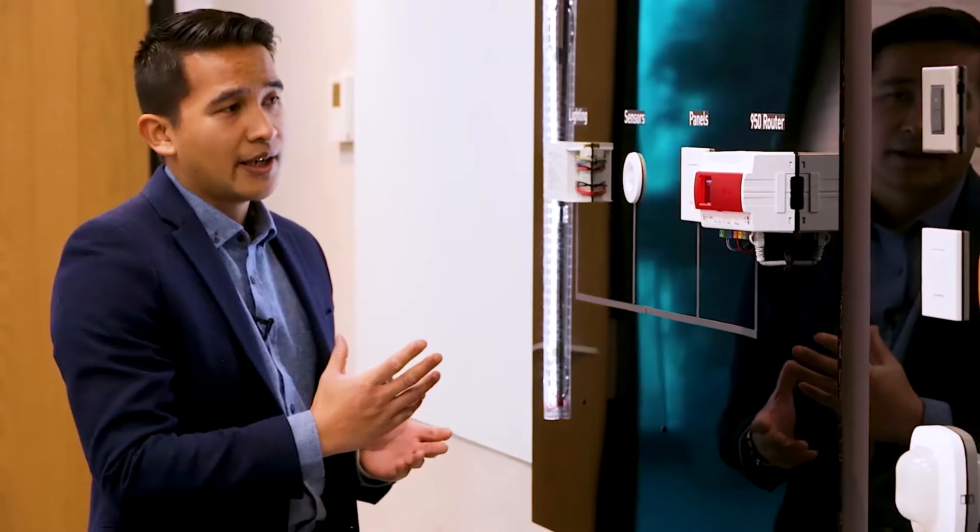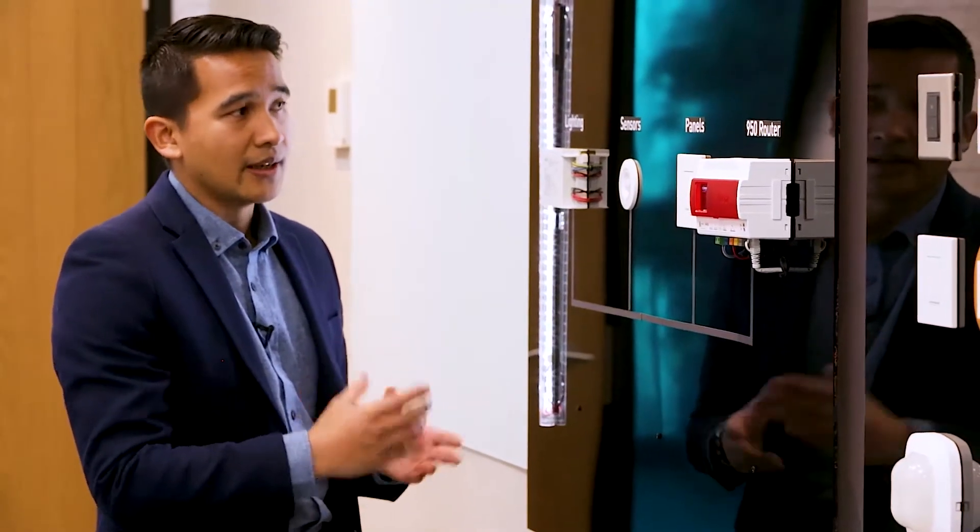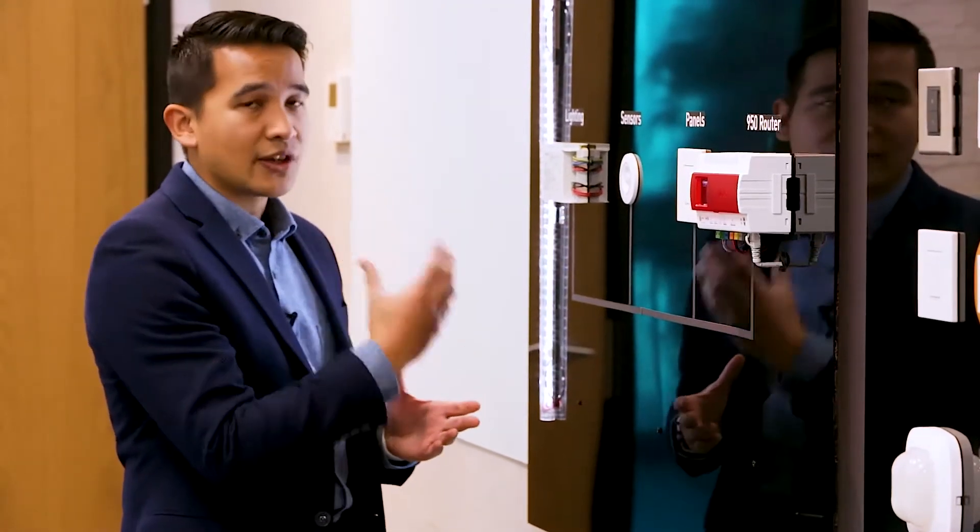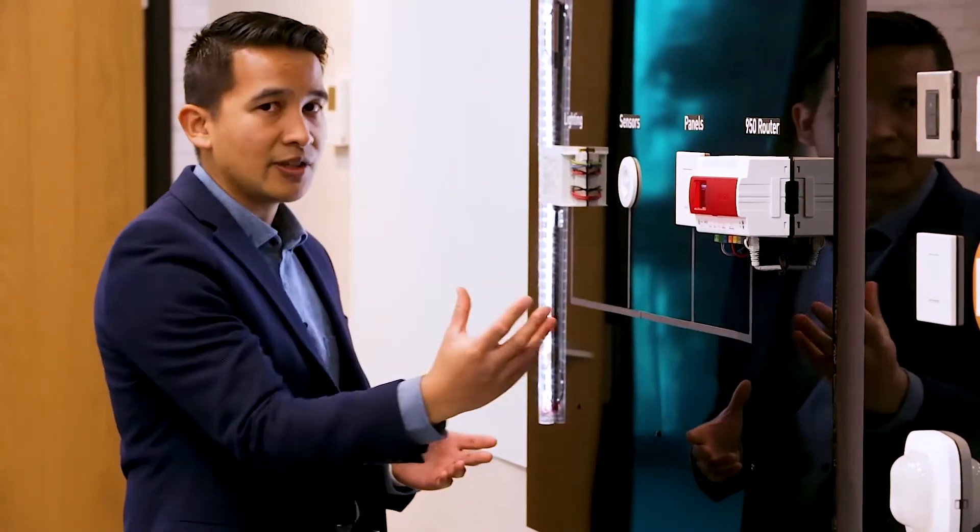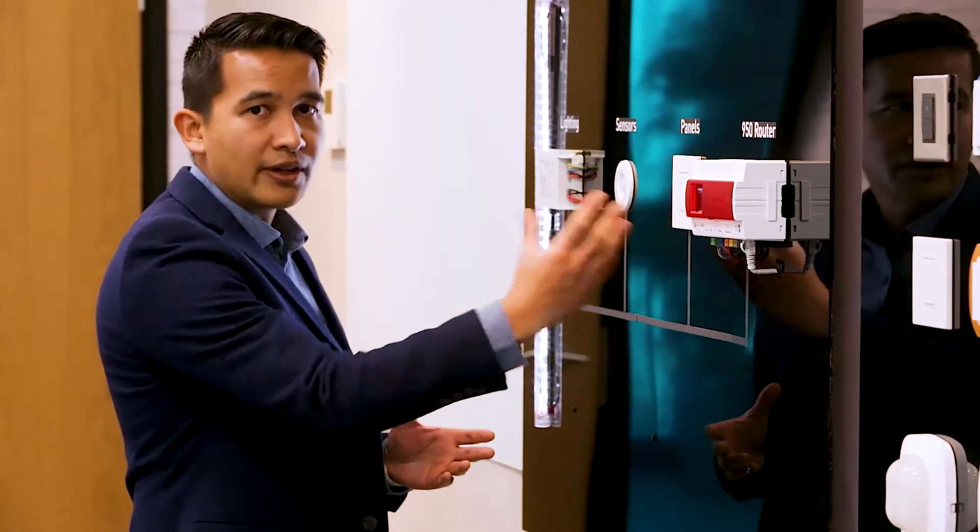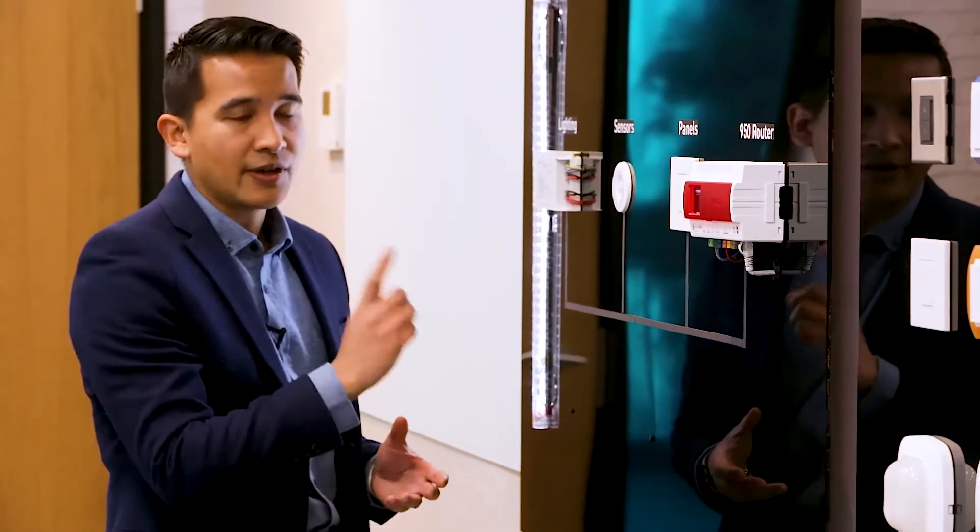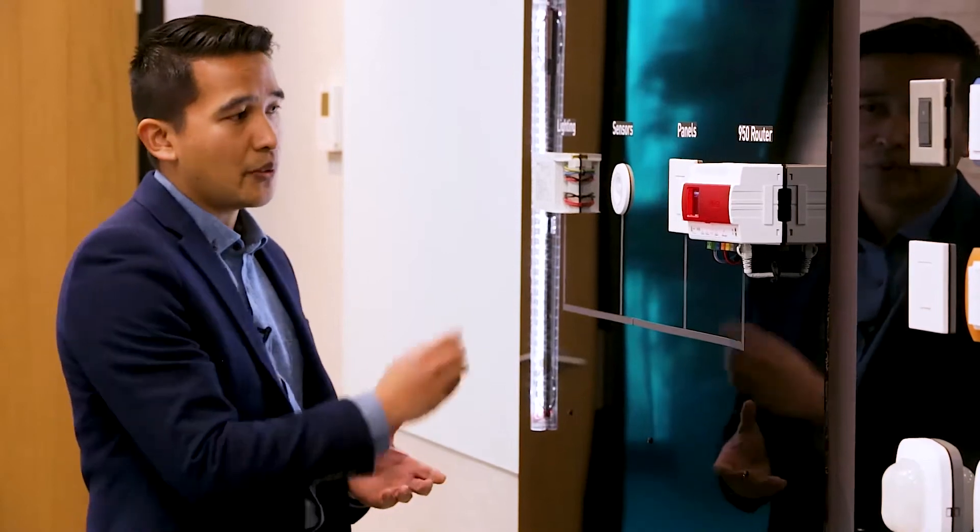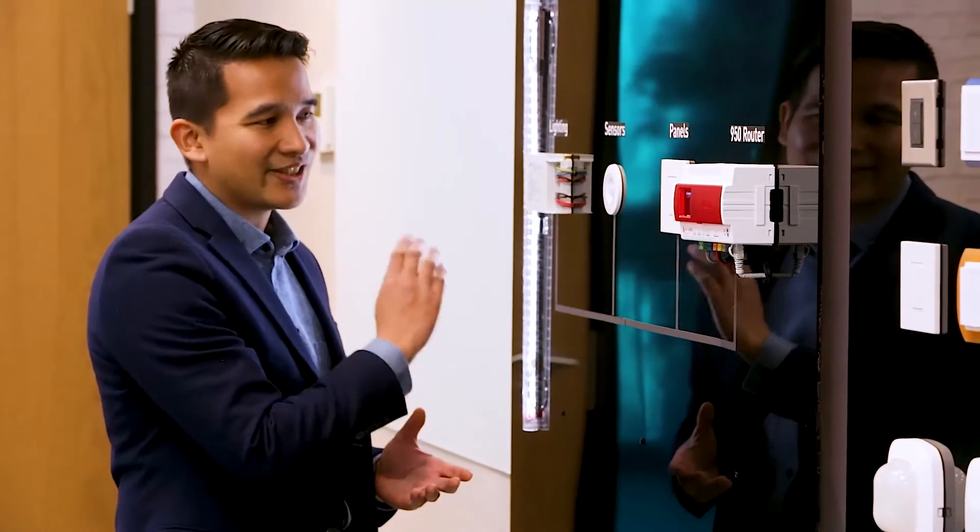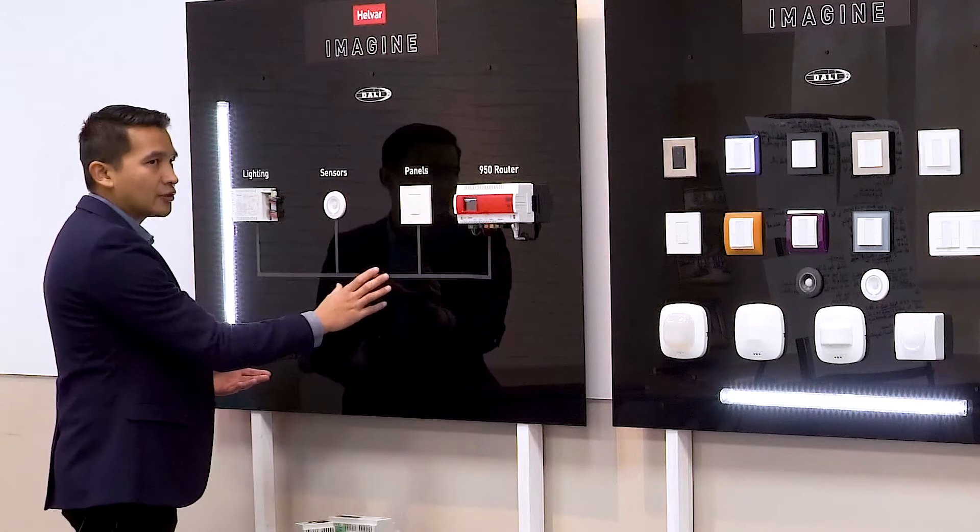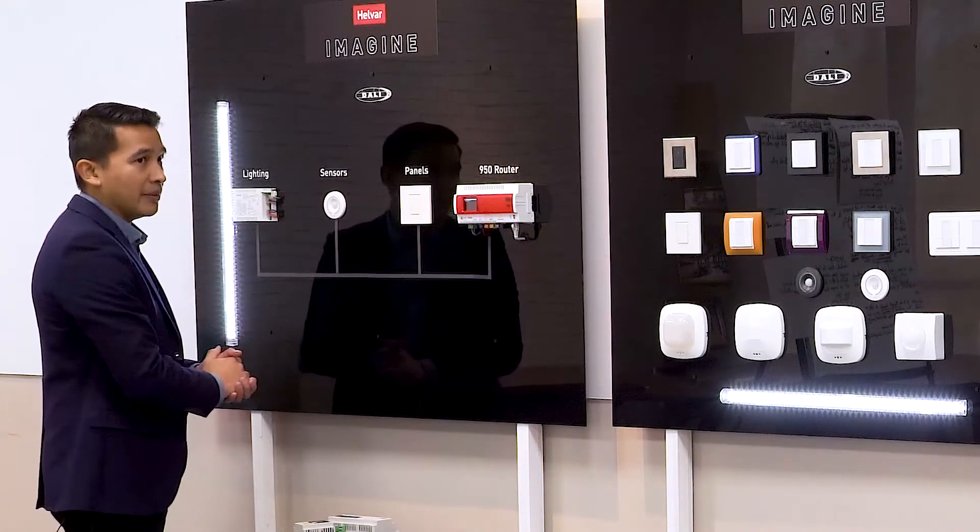And then lastly, which we think is the game changer here, is that it standardizes the communication between your lighting and your application controller with control devices on the network. This is the first time in history where we have a dedicated standardized protocol between lighting and controls all on the same network.